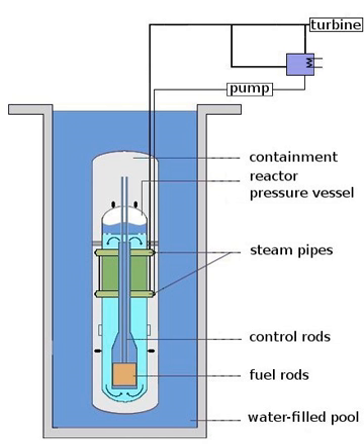Control rods are usually combined into control rod assemblies — typically 20 rods for a commercial pressurized water reactor assembly — and inserted into guide tubes within a fuel element. A control rod is removed from or inserted into the central core of a nuclear reactor in order to control the number of neutrons which will split further uranium atoms. This in turn affects the thermal power of the reactor, the amount of steam generated, and hence the electricity produced. The control rods are partially removed from the core to allow a chain reaction to occur, and the number of control rods inserted and the distance by which they are inserted can be varied to control the reactivity of the reactor.